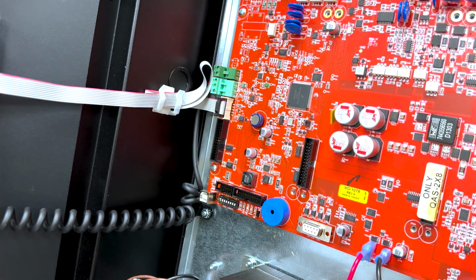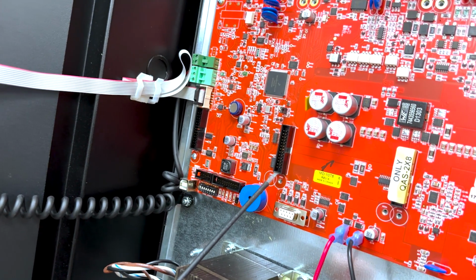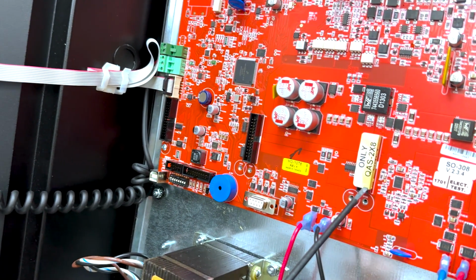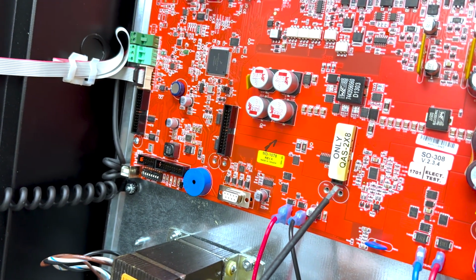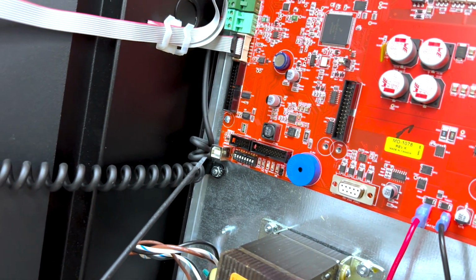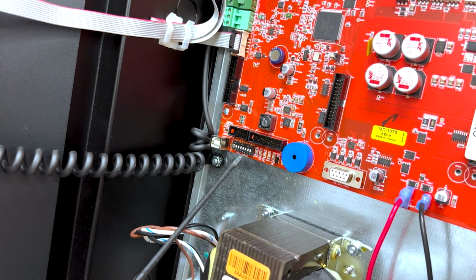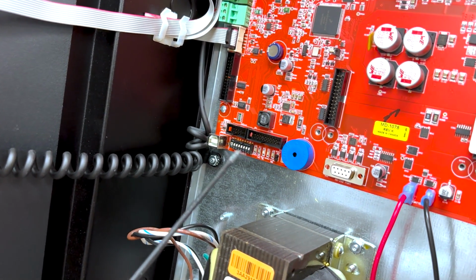In the middle of the MD1078, we have 3 connection ports. P5 and P6 are reserved for amplifiers 1 and 2, and P7 is reserved for the QAS 2x8 splitter card. At the bottom left-hand corner, we have the USB Type-B port for programming the panel, and next to that, we have the RS-485 address dip switch bank for addressing the panels.